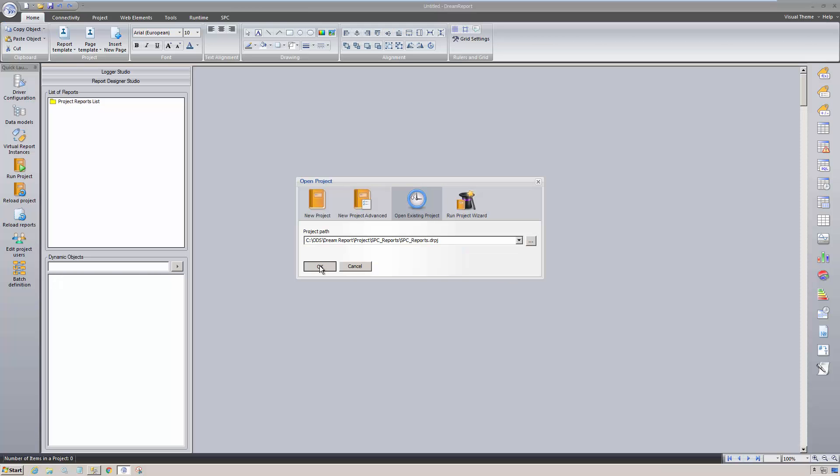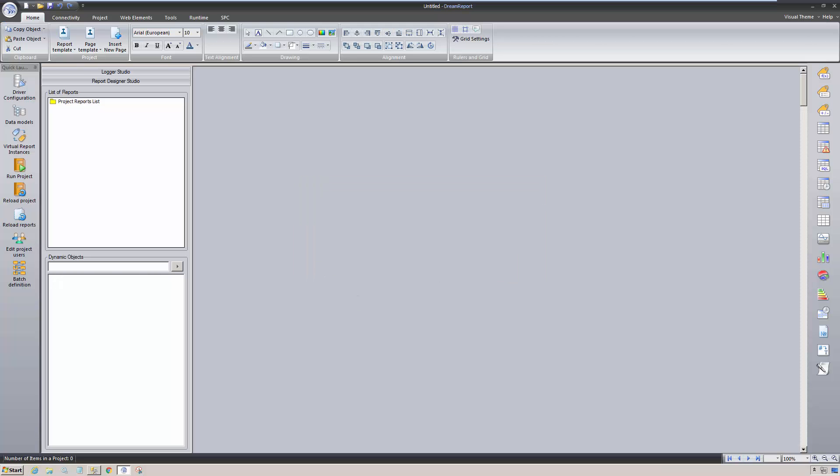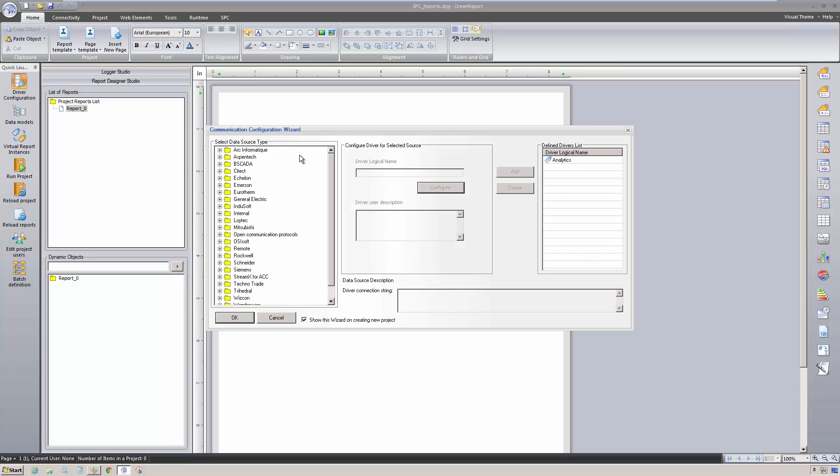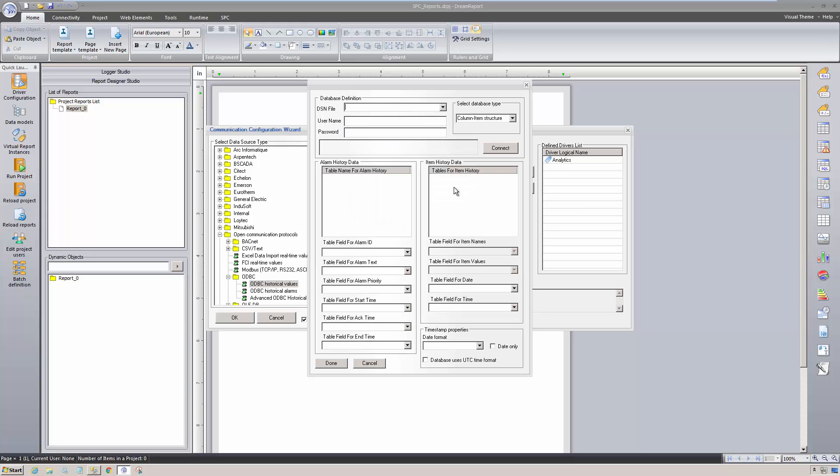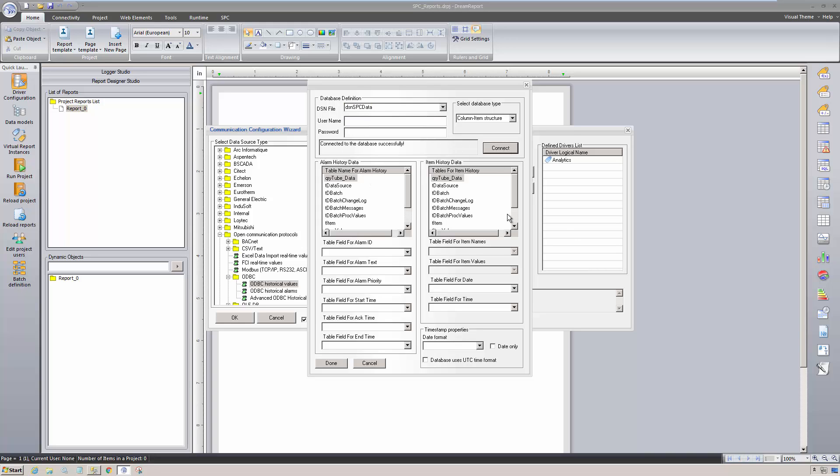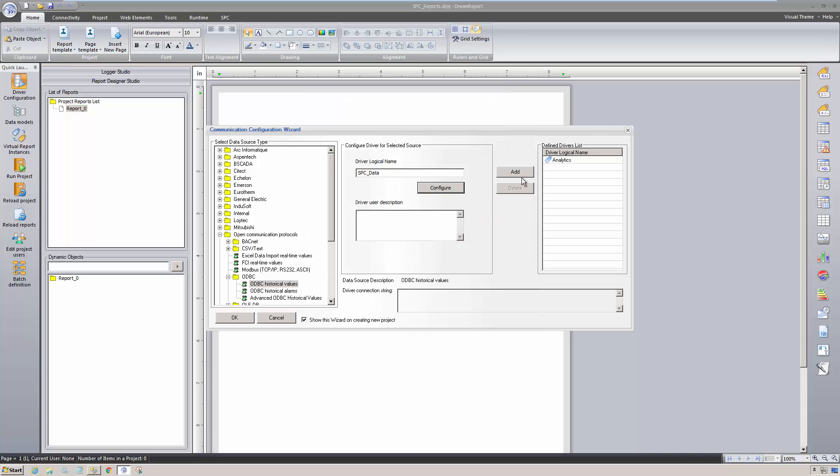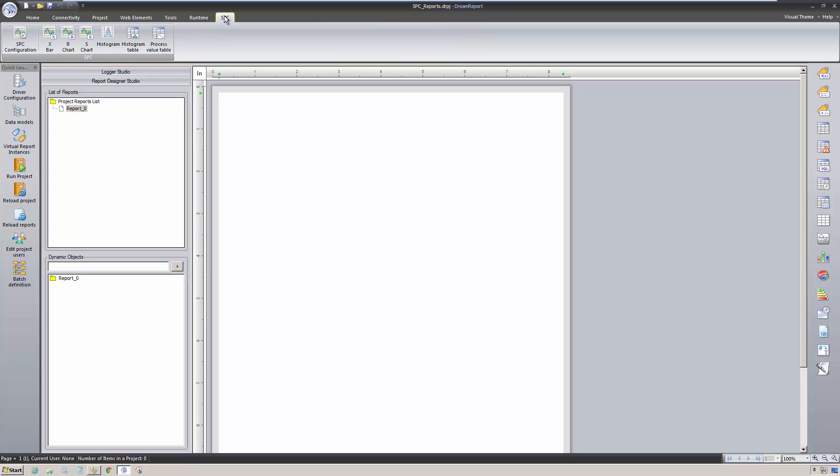I'm going to open DreamReport Studio to a blank project and configure a communication driver to my SPC data source. Since my data happens to be stored in a database, I'm going to open and configure an instance of the ODBC historical values driver, located under the Open Communications Protocol folder. I'll give this instance of the driver a unique name, and then select an ODBC data source name, or DSN, that I've already configured in the Windows ODBC manager and connect to the database. DreamReport lists all the tables and the views in the database. I'll select the table containing my SPC data, and simply tell DreamReport which field in the table contains the logged values date and timestamp. I'll click OK, and then add the configure driver to the list. At this point, we're ready to start defining our SPC configurations.